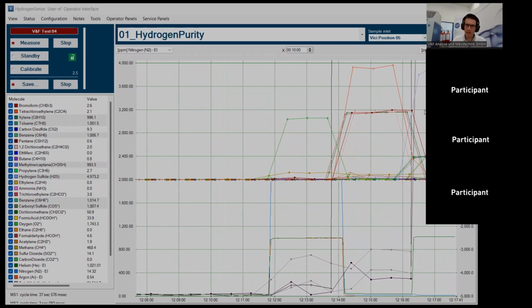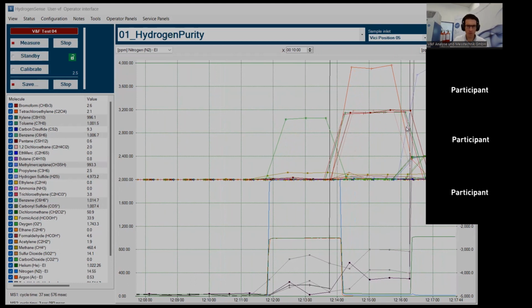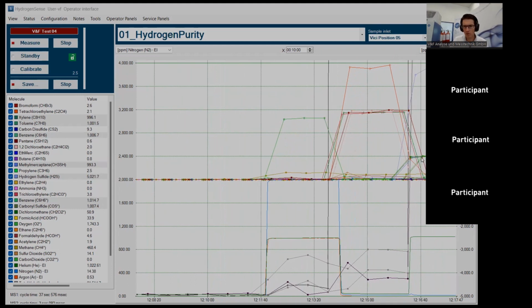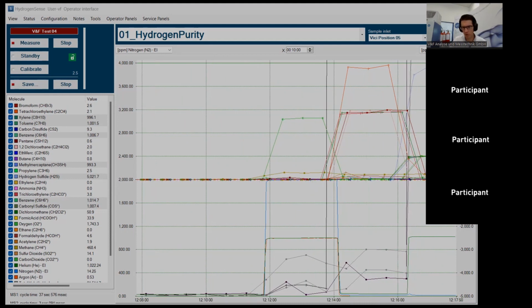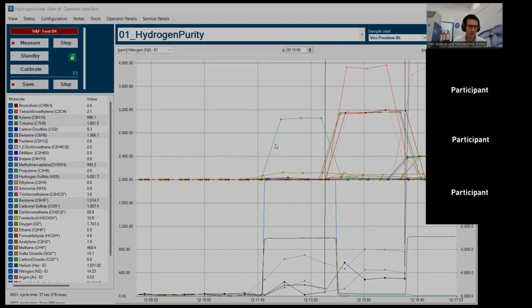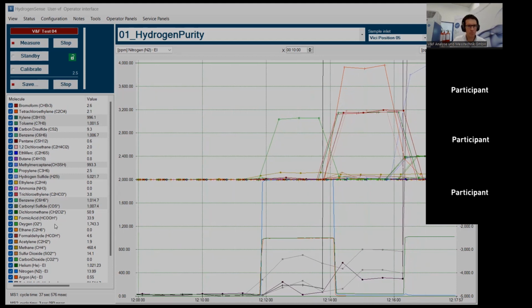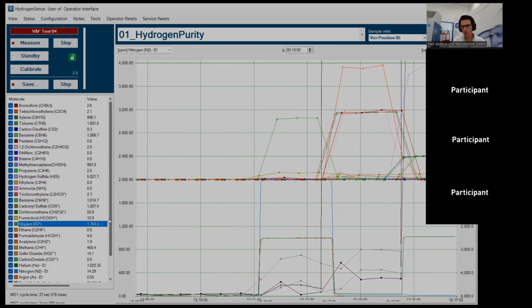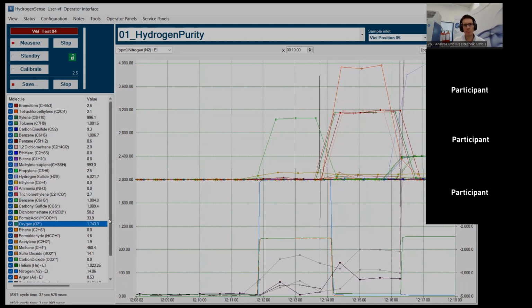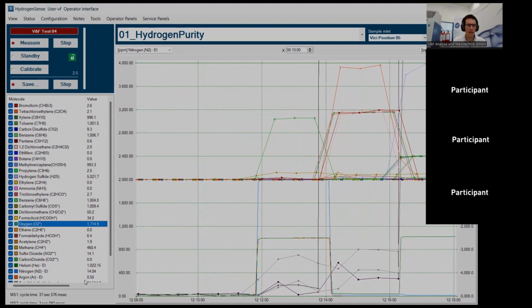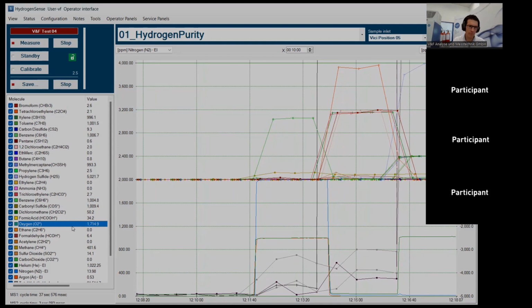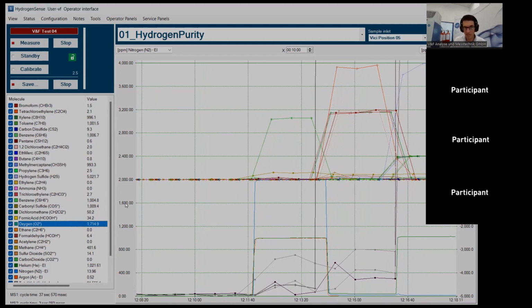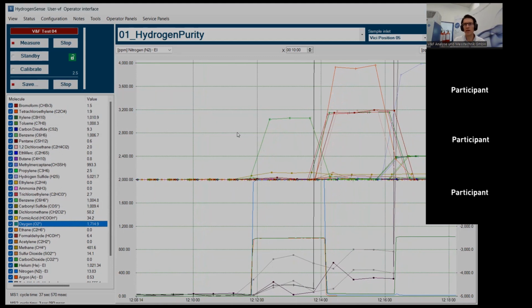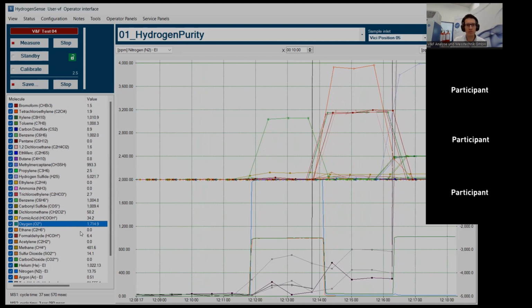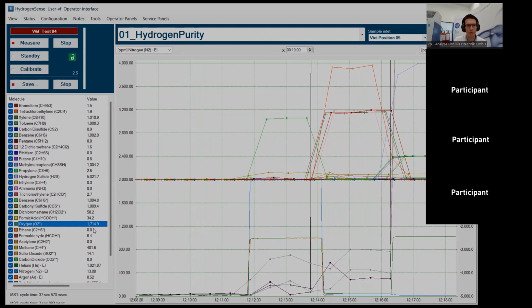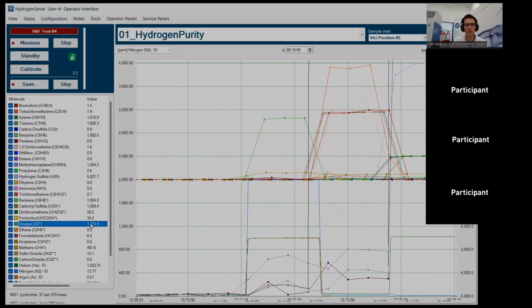once new sample lines are attached, the initial flush time is one of the most crucial things which might cause you issues in response time, or also really in final saturation. From our experience, the most problematic compound is oxygen here, because usually when you attach a new gas or you have an improperly flushed line, you will have ambient air in that line, meaning that ambient air contains around 20.8% oxygen. So in order to flush all of that out, that is something that needs to be done very diligently in order to get a proper reading for the oxygen content in the gas that you want to analyze.